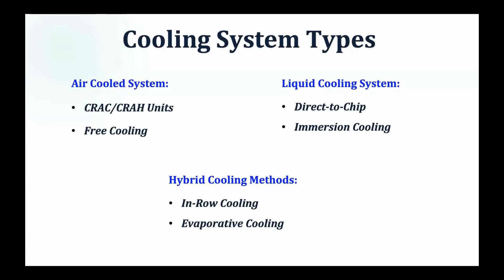Now, what are the standards used to define the cooling systems of a data center? ASHRAE Technical Committee 9.9 is one of the prominent authorities providing guidelines for designing cooling for mission critical facilities, like data centers, clean spaces, and some electronic equipment. The primary purpose is to have common standards across the board for designing cooling for data centers and critical facilities, so that equipment interoperability is ensured, since one manufacturer may use something different from another.